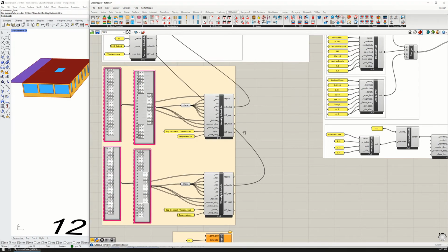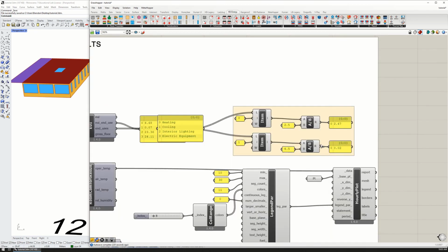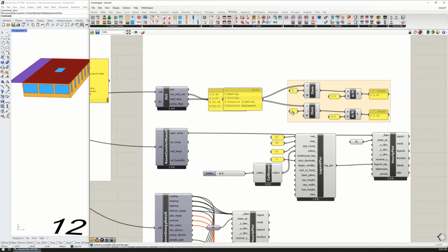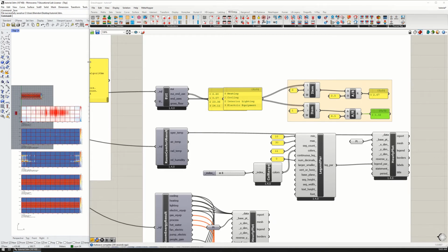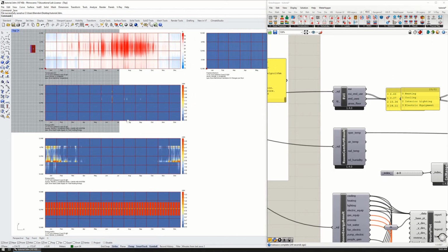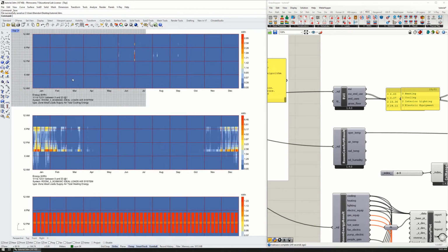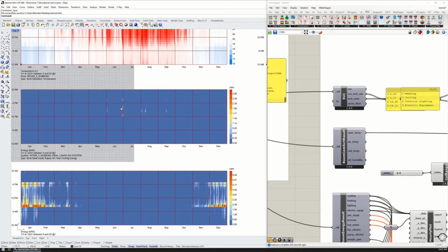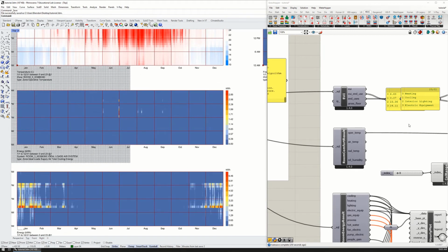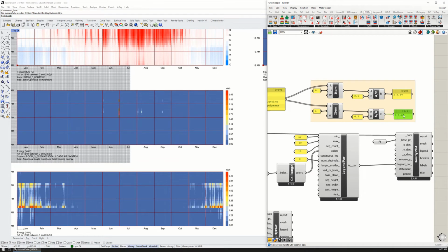So after running this, you'll see that the heating and cooling energy have both been reduced, the cooling energy dramatically so, and then I realized I made a mistake. The way that I realized this is that if I look at the graphs of cooling and heating, you can see that the cooling barely comes on and the heating comes on throughout the winter when it's occupied. Well, the fact that the cooling barely comes on is interesting and sort of relates to this very low EUI that we're getting.